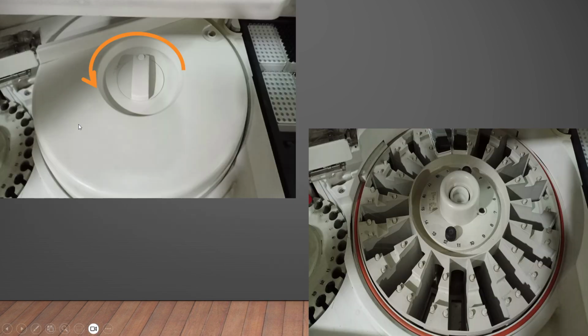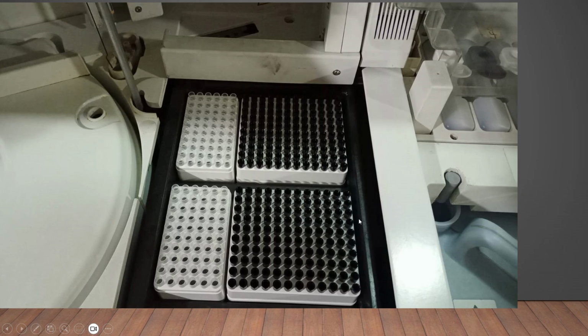Okay, so this is the reagent disc. The reagent disc has got a lock, which when you turn to this side, you can lift it up. When you lift it up, this is the reagent disc where all the clear reagents are placed. Okay, so this is the cups and tips tray. They are kept in this fashion. The tips are the larger ones, whereas the cups are the smaller ones, and this is the mechanism by which it picks up the cups and tips, right?